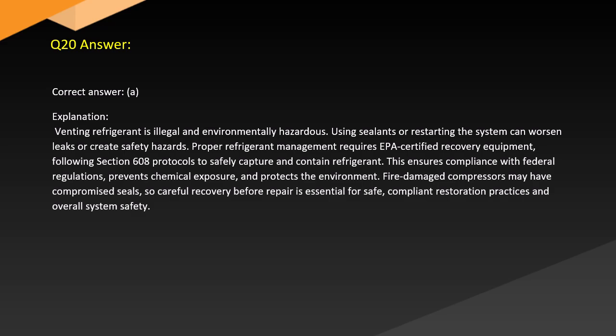Answer. Correct answer: A. Explanation: Venting refrigerant is illegal and environmentally hazardous. Using sealants or restarting the system can worsen leaks or create safety hazards. Proper refrigerant management requires EPA-certified recovery equipment following Section 608 protocols to safely capture and contain refrigerant. This ensures compliance with federal regulations, prevents chemical exposure, and protects the environment. Fire-damaged compressors may have compromised seals, so careful recovery before repair is essential for safe, compliant restoration practices and overall system safety.